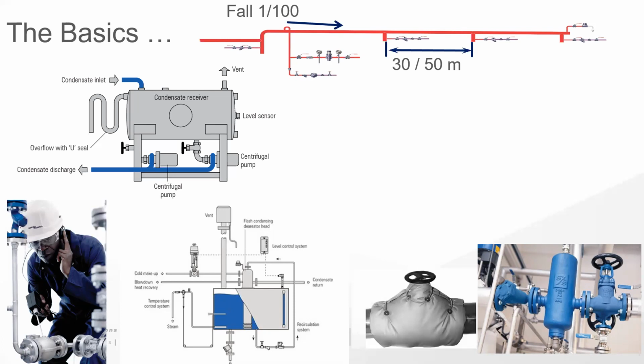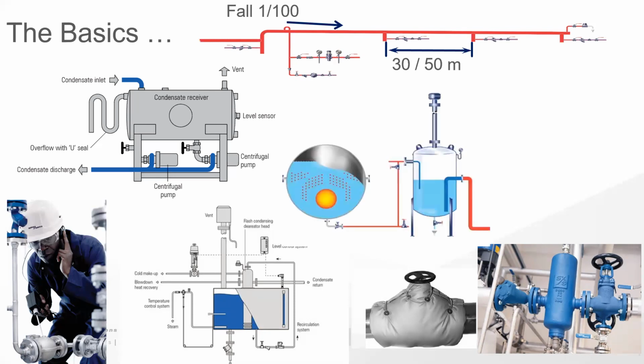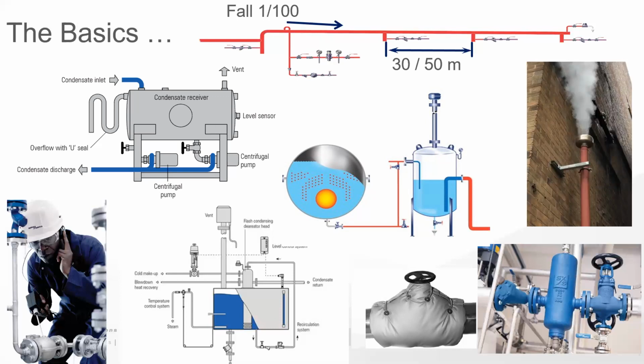Ensuring that the insulation is kept at the optimum standard to reduce the heat losses in the distribution pipework. Ensuring that we've upgraded the boiler blowdown controls, moving away from manual blowdown to automated blowdown, to ensure that the energy that needs to be lost and purged to waste to keep the boiler at an optimum point is kept at the lowest point prescribed by the OEM. Any more is an inefficiency. But also ensuring that the flash steam that is vented away to atmosphere to protect the condensate system and the condensate pumps is kept to an absolute minimum, or better still, that we've got solutions in place to recover it.